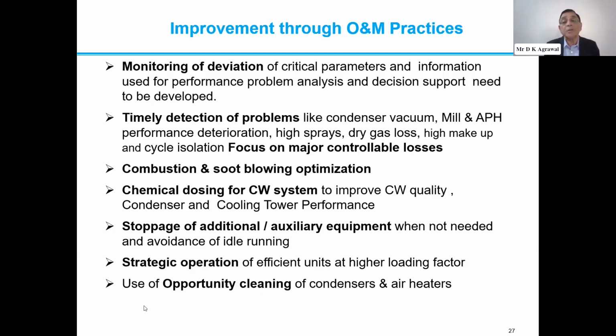But at the same time, in many places we have seen there should be a proper trade-off between the replacement of the rollers and auxiliary power consumption. So many aspects have to be seen from that point of view. For condenser vacuum, we also have to take care of the water quality and make sure it is not creating too many deposits on the tubes. There are going to be opportunities for cleaning during the overhauls, but it has a direct impact, and as we discussed some time back, very high implications in terms of heat rate. And combustion and soot blowing optimization is also important, sometimes people are religiously just following that key.